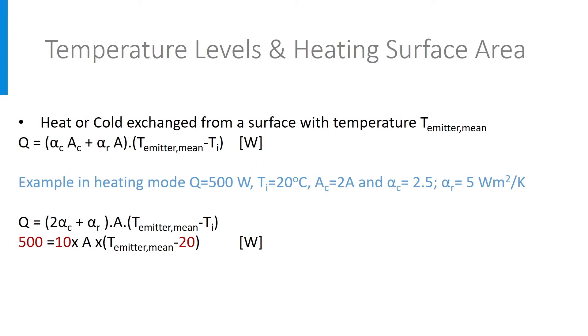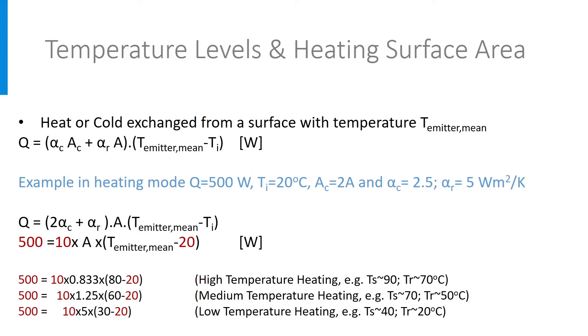In the first example, the radiator has a mean temperature of 80 degrees Celsius. The hot water will for instance enter the radiator at 90 degrees and leave it at 70. With this temperature, a radiator surface area of 0.83 square meter is needed.